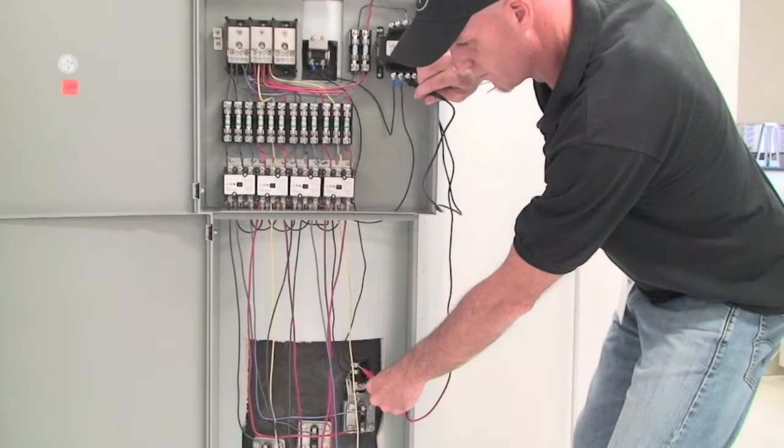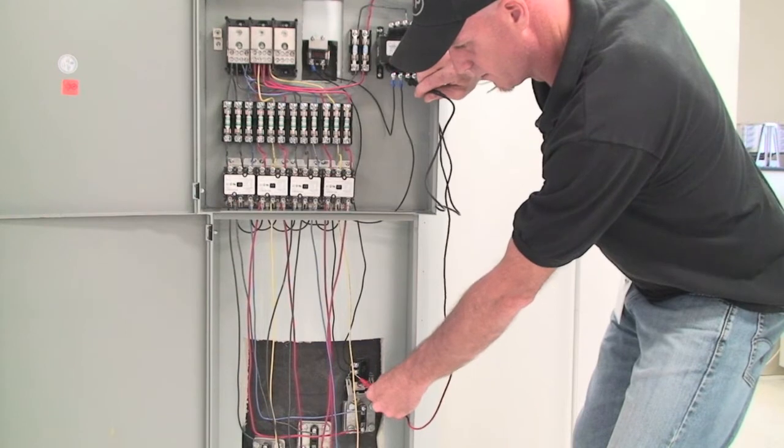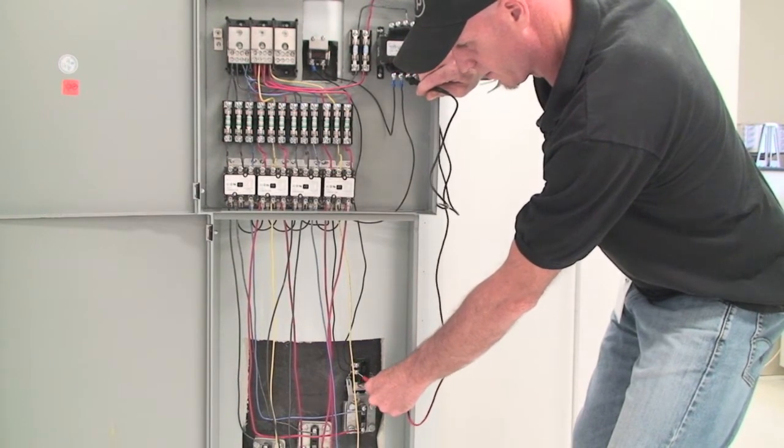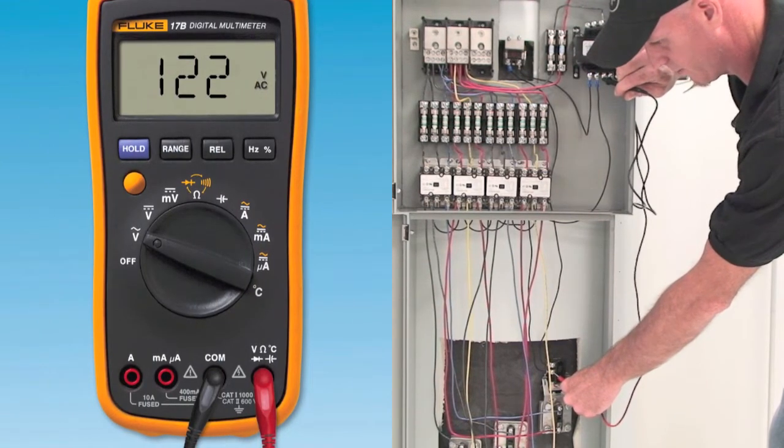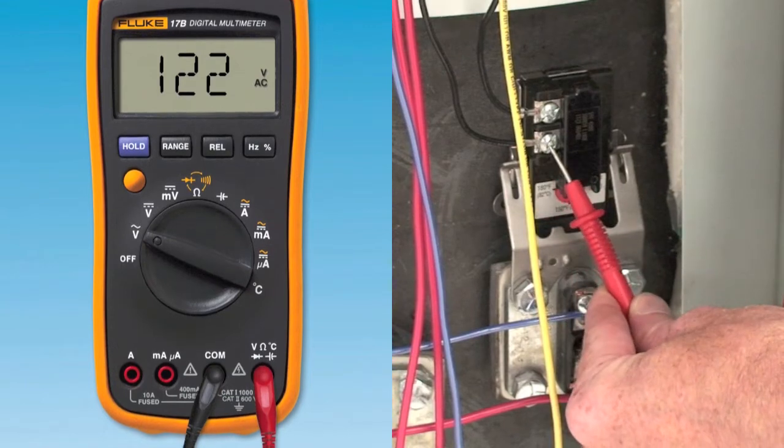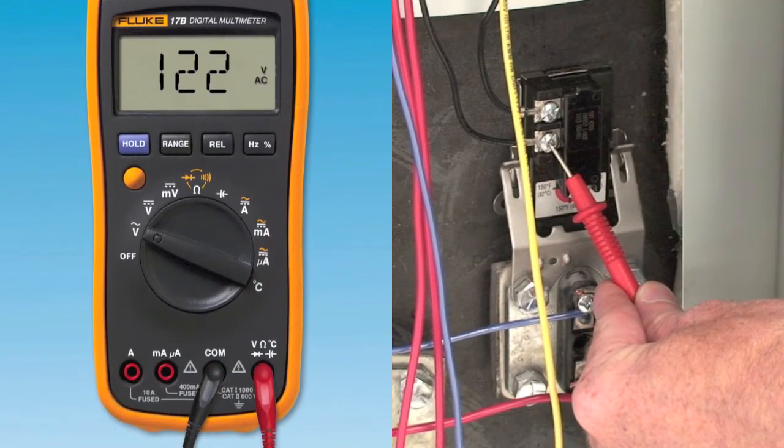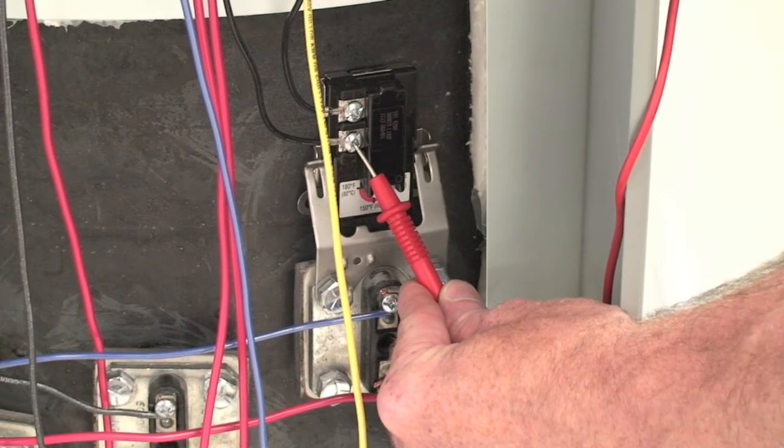If 120 volts AC is present, move the meter lead from the upper terminal on the thermostat to the lower terminal on the thermostat. If 120 volts AC is present on the lower terminal, the thermostat is in the closed position and is operating properly.